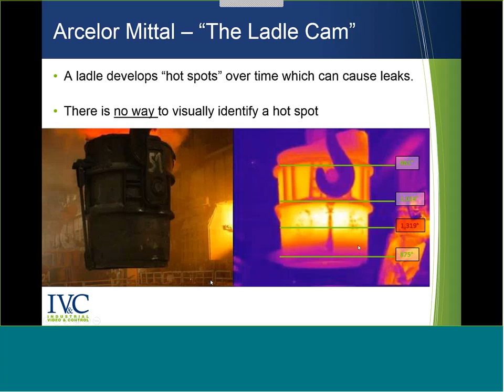This temperature can also be sent back to Wonderware, the Wonderware historian, to historize all that data, and we'll create alarms on thresholds. So if a hotspot is developing, we'll immediately send an alarm to your Wonderware system and create a video clip, sending that to the operator to show them exactly where that hotspot is.